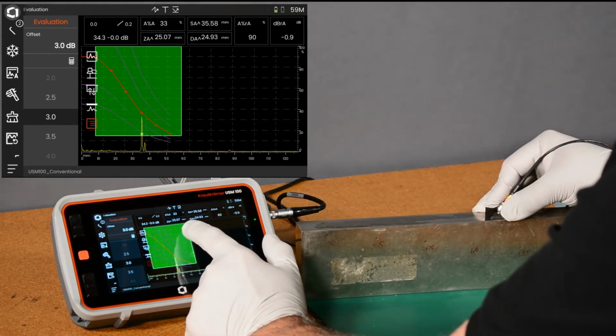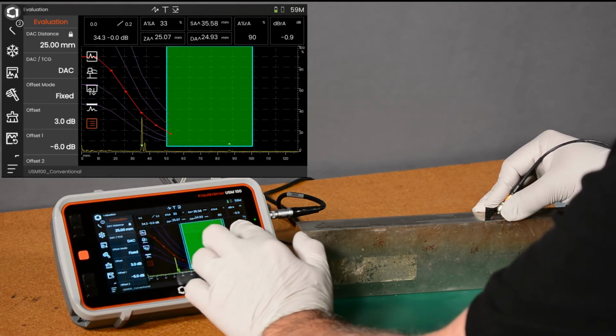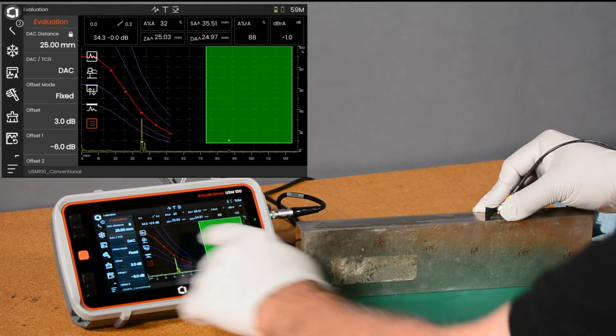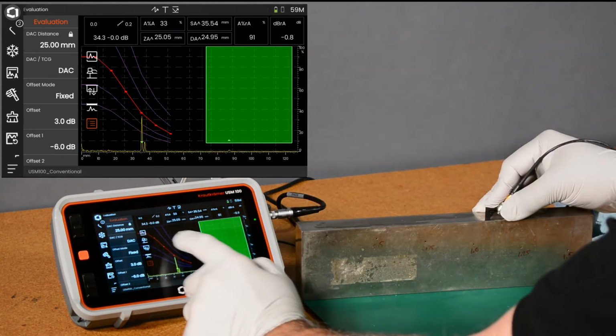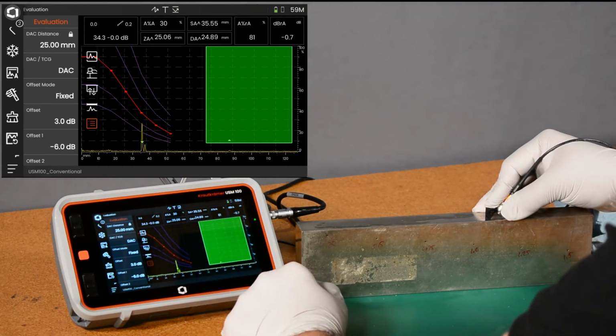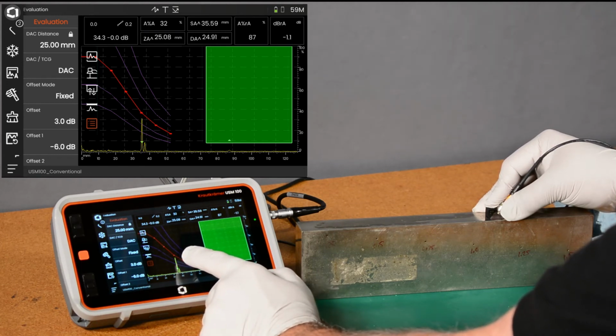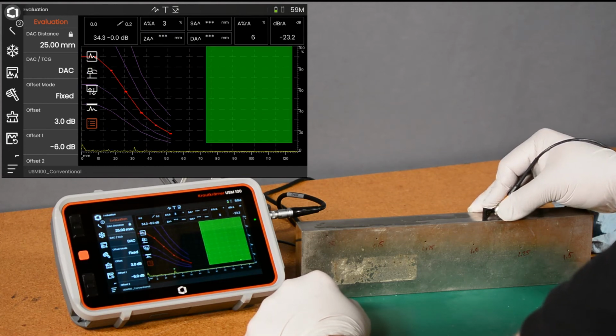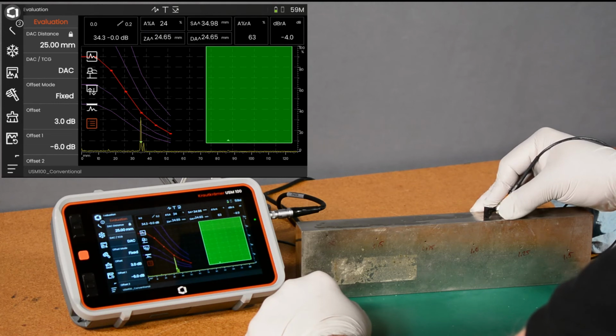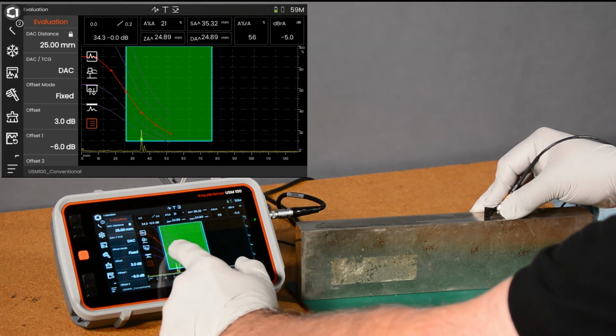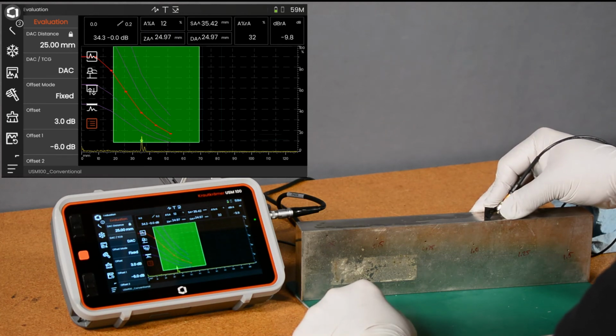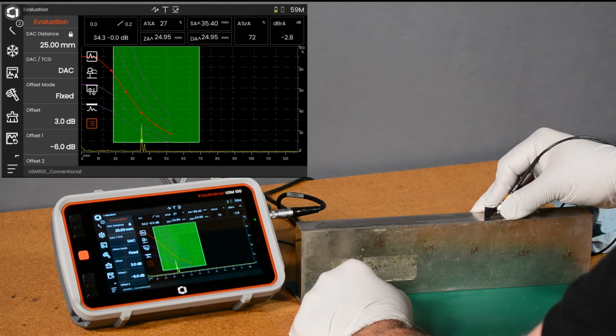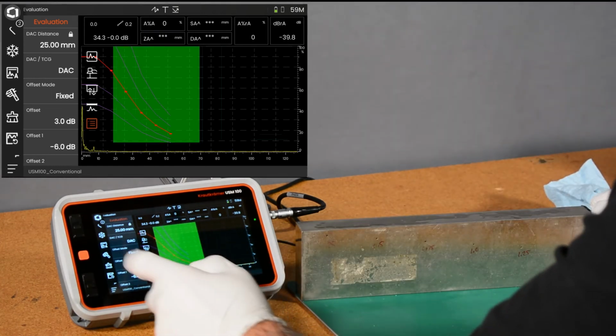And now it's a little difficult to see against the green gate. But if I move the gate out of the way, you can see we have 4 curves that are parallel to our reference curve. The reference curve is there in red. And in violet, we have 4 parallel curves. And those curves are separated by 3 dB from our reference echo. So you can tell at a glance, as I move the probe, as I approach the peak, come off the peak, you can tell at a glance at the A-scan, there's 6 dB down from our reference curve. There we go, so about 6 dB. Our dB relative to the reference is down about 6. There's a bit down about 3. There's back to our reference echo. Okay? So that's the offset curve feature.